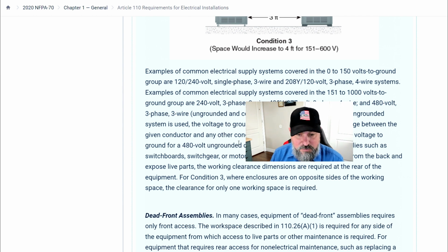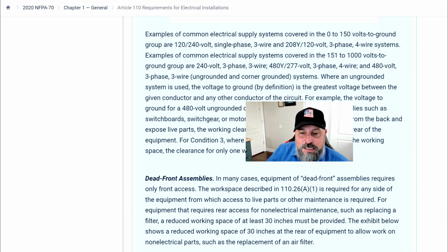For condition 3, where enclosures are on opposite sides of the working space, the clearance for only one working space is required. So if you have them on either side, what that's saying is you don't have to double it and make it 8 feet. Because they are requiring that you only have one open at a time.